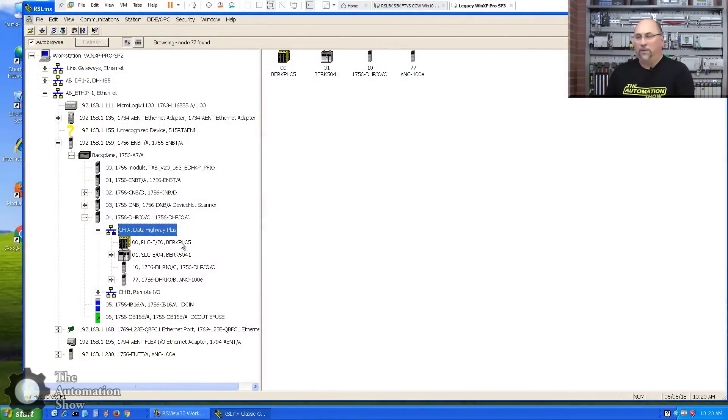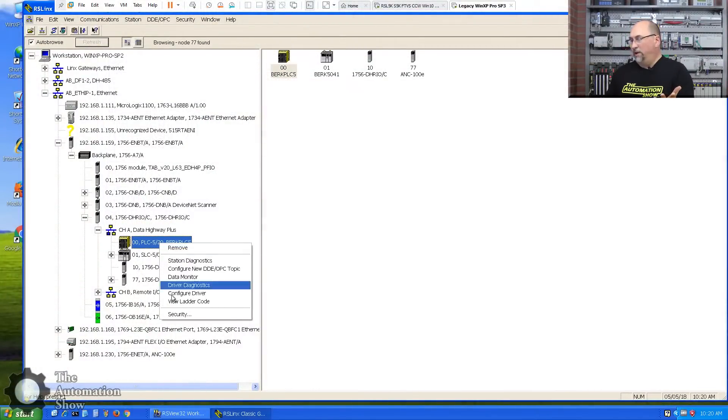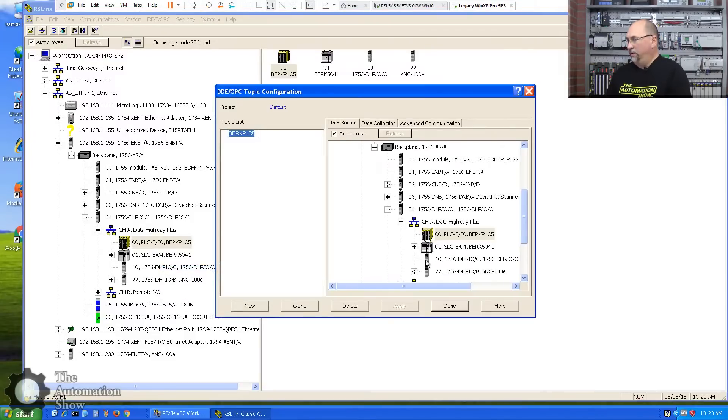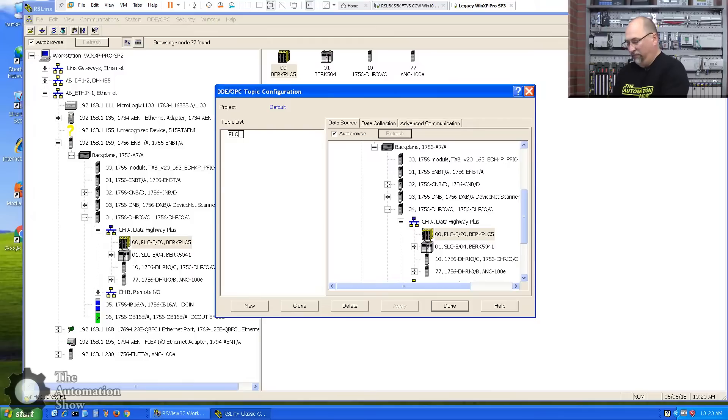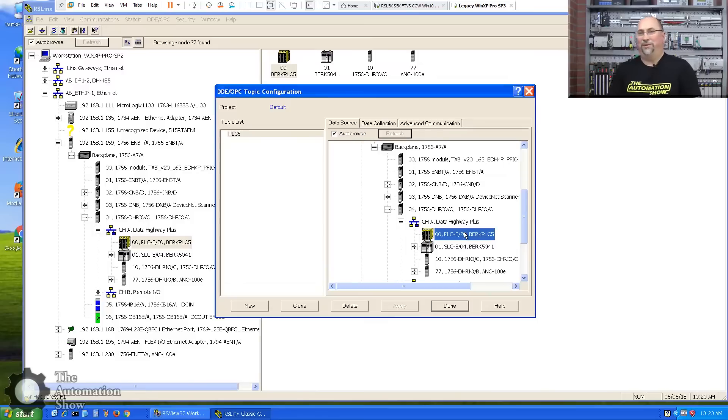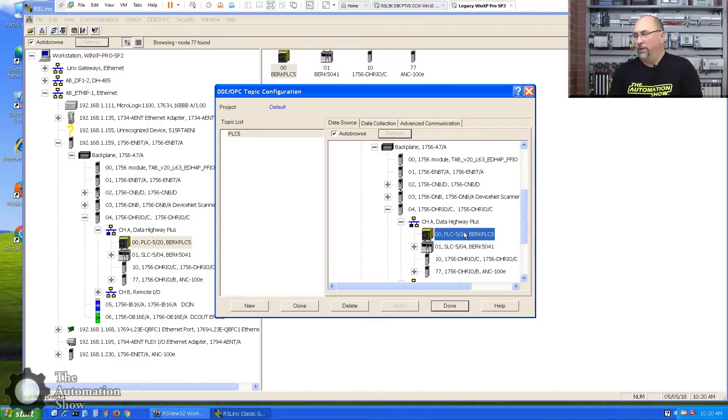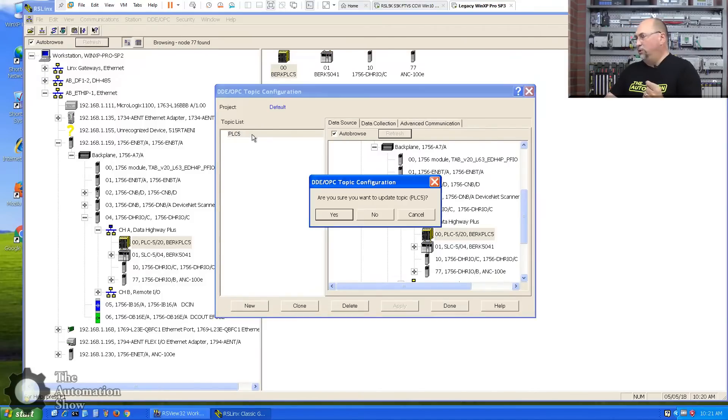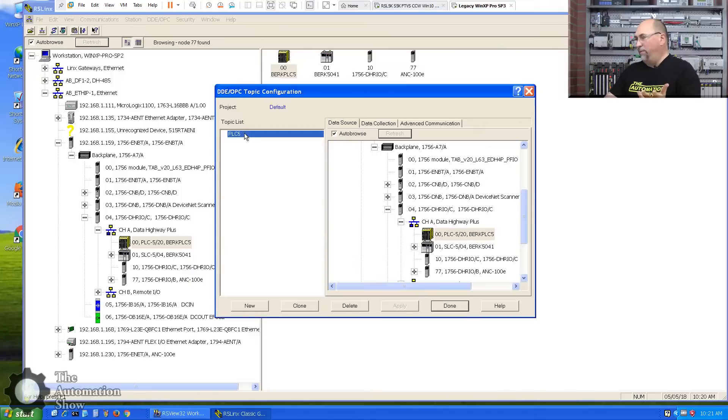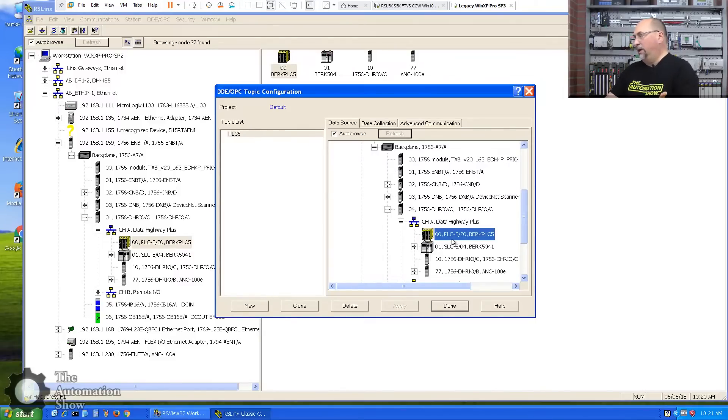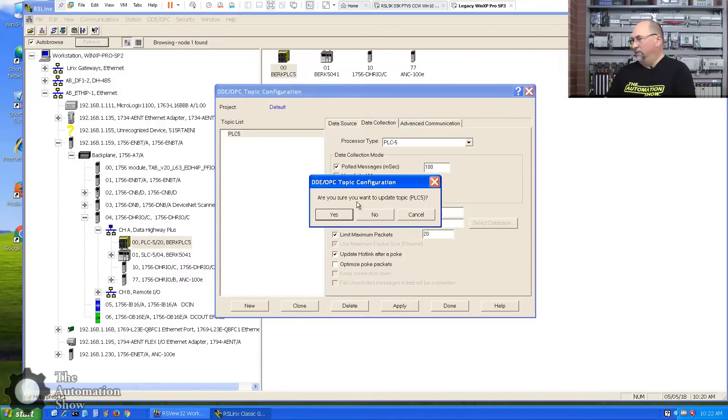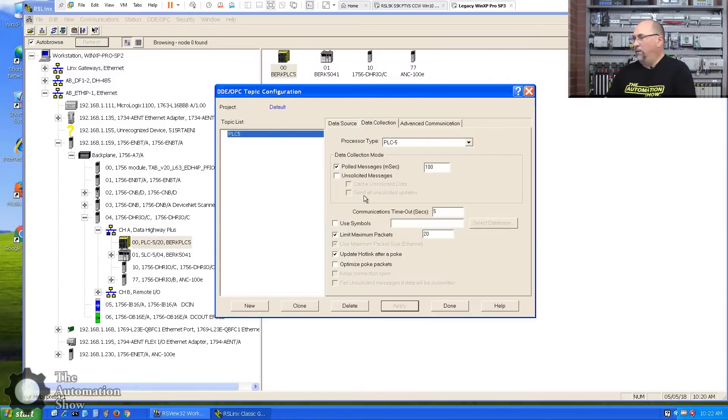So having said that, let's go ahead and set up our OPC. The easiest way is to right-click here. I'll right-click on the PLC5 and I will go to Configure New DDE OPC Topic. And I'm going to call this, I'm actually going to call it PLC5. And you can see the PLC5 is already selected, and you may see that this is very similar to RSLynx Enterprise or FactoryTalk Lynx now. And this is really the kind where the GUI came from for RSLynx Enterprise. The one thing I like to do here, it's asking me if I want to apply. The one thing I'd like to do here, besides just making that relation between the topic, which would now be called the shortcut in RSLynx Enterprise, and the controller, is I like to up this data collection. I like to make this 100 milliseconds instead of 1,000 milliseconds.